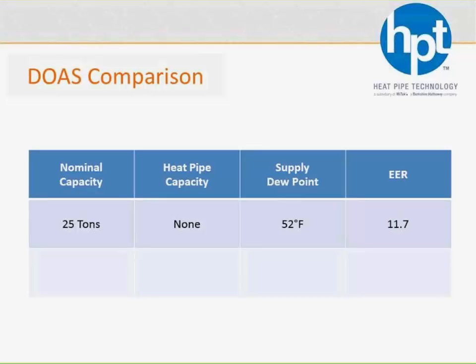So let's take a look here. This is a 25-ton nominal tons DOAS unit. In this case, let's say it doesn't have a heat pipe on it. It's going down to a 52-degree dew point, so the EER for that 25-ton unit is 11.7. Well, now let's say, again, we've done 5 tons of pre-cooling. So to get 25 tons of net cooling, you only need now a 20-ton DOAS unit. We're accomplishing 5, it's accomplishing 20, you're getting 25 tons of cooling.